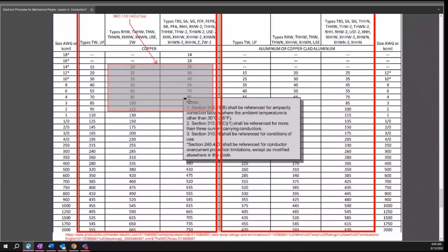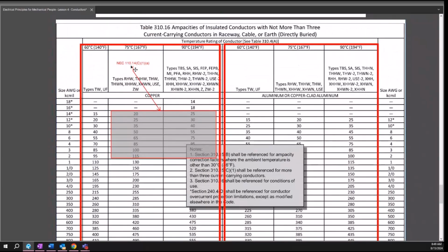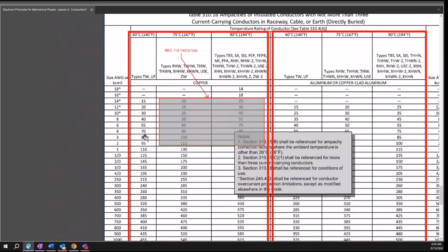The next thing I want to talk about was in the NEC 110.14(C)(1)(a). At a high level, it talks about if your stuff is rated at 100 amps or less, you have to assume 60C terminals. If you have not read this, or anybody on YouTube, if you're not familiar with this, go read it. I'm just giving it a high level, not really doing it justice, but go read it. And in my Uglies book and in my NEC copy, I have basically marked out this section of the code to help me remember that in anything less than 100 amps, I have to be rating off of the 60C column. Just understand, if you're number 2 or below, pull it off the 60C column.